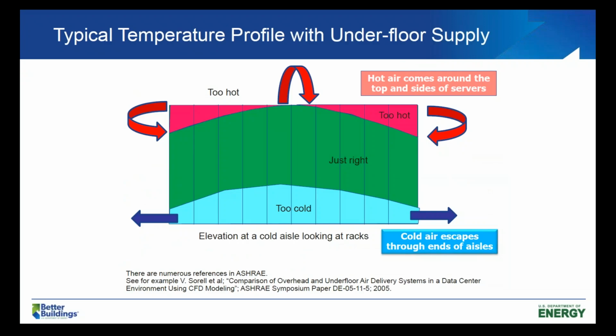All right, so here is an elevation view of a row of racks, and this is a very common distribution problem. You've got air that's colder than it should be in the center. At the bottom center of the rack, you've got that green band of temperature that's in the proper range, in the recommended range, and then at the tops, and typically worse at the ends of the racks because the hot air comes around the end as well as over the top, you've got areas that are too hot. And then you've got bypass air there at the bottom escaping around the ends of the aisles. Next slide.